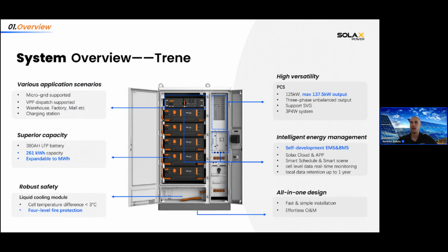For the TRENE, you have a different battery cell capacity compared to the air-cooled version. It can also be expanded to 1 megawatt-hour capacity in total with multiple pieces. And for the PCS, you can have 125 kilowatt maximum AC output, and you can reach 10% more in peak version. So it will be 137.5 kilowatt.